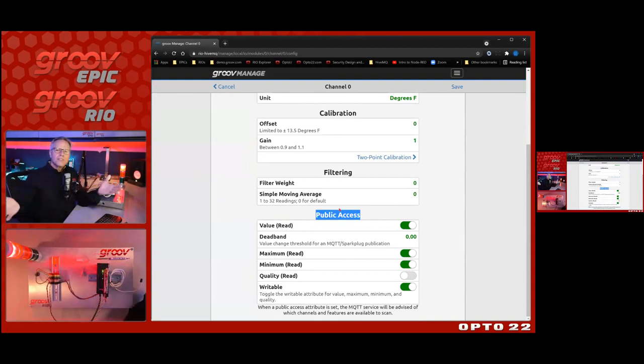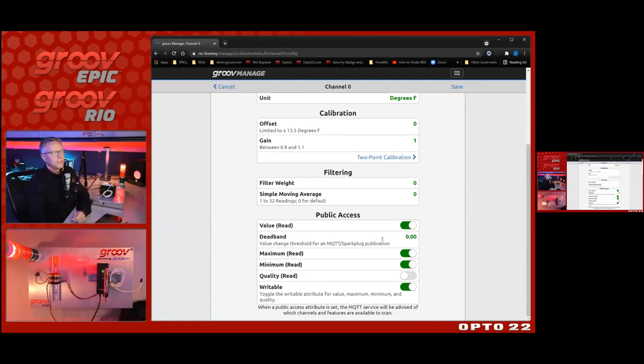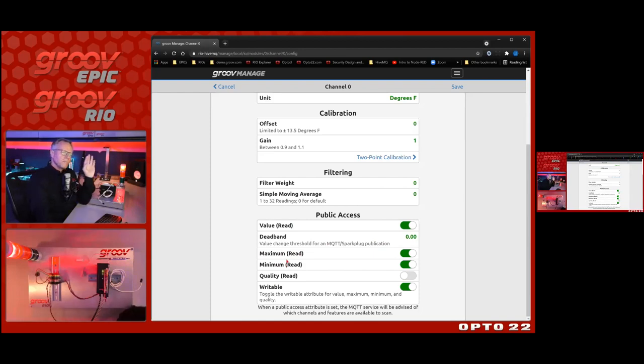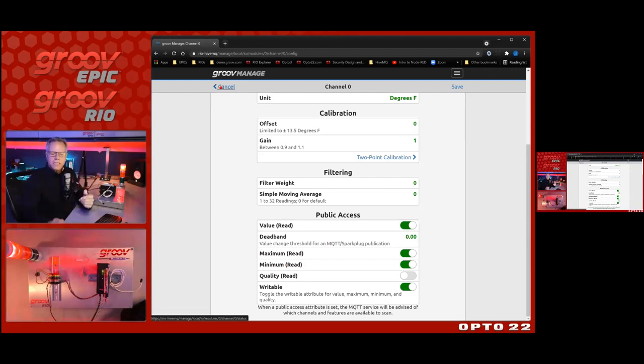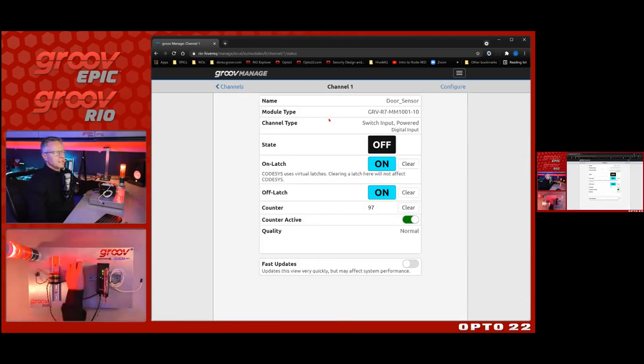Under Public Access I configure which data values to send under that tag name. For the temperature sensor I'll send the temperature value, and because we're using MQTT and Spark Plug B, I'll only send on change — with dead band zero, any temperature change publishes a message to the broker. I'll also send the minimum and maximum values ever reached while the device is powered on, so one sensor can have multiple data values. The door sensor is configured as a switch input and a counter, so as I move the door switch back and forth it counts how many times that happened.